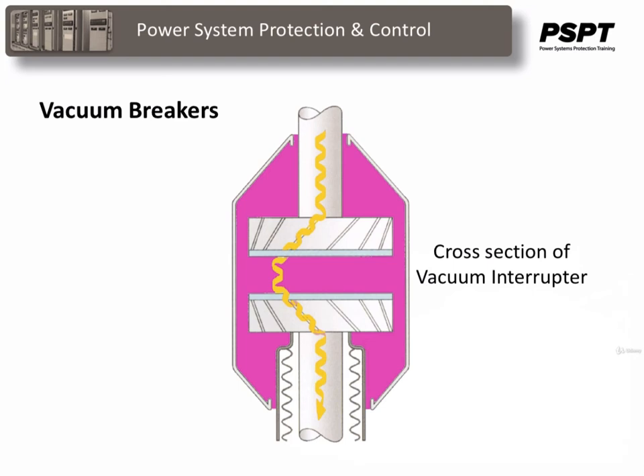At current zero, this vacuum arc is extinguished and the conducting metal vapor is recondensed on the contact surface. At this point, the contacts are already separated, hence there is no question of revaporization of the contact surface for the next cycle of the current. That means the arc cannot reestablish again. In this way, vacuum circuit breakers prevent the reestablishment of the arc by producing high dielectric strength in the contact gap after current zero.